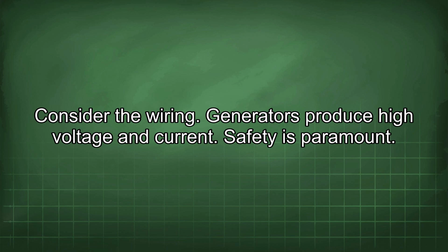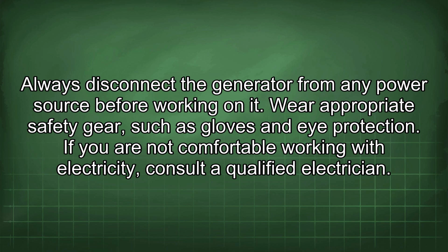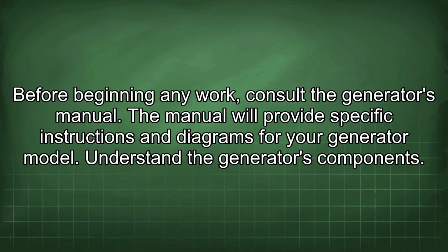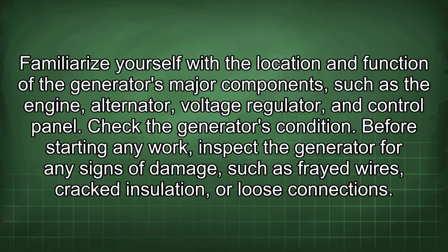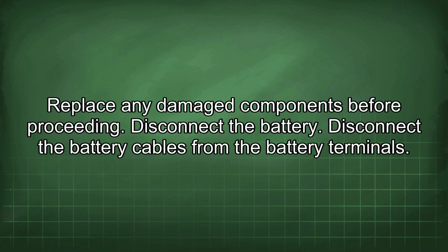Consider the wiring. Generators produce high voltage and current. Safety is paramount. Always disconnect the generator from any power source before working on it. Wear appropriate safety gear, such as gloves and eye protection. If you are not comfortable working with electricity, consult a qualified electrician. Before beginning any work, consult the generator's manual. The manual will provide specific instructions and diagrams for your generator model. Understand the generator's components. Familiarize yourself with the location and function of the generator's major components, such as the engine, alternator, voltage regulator, and control panel. Check the generator's condition. Before starting any work, inspect the generator for any signs of damage, such as frayed wires, cracked insulation, or loose connections. Replace any damaged components before proceeding.